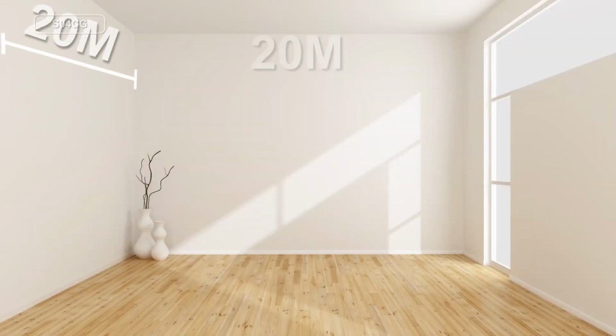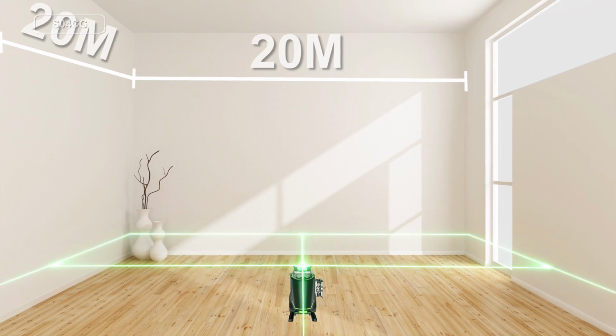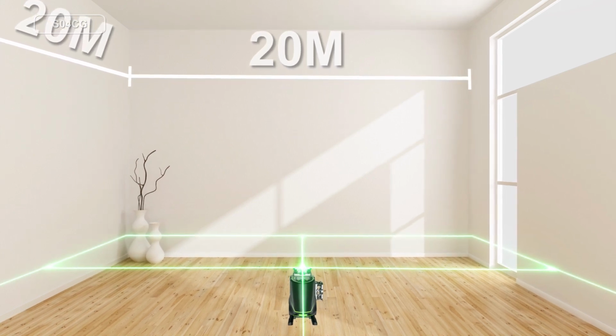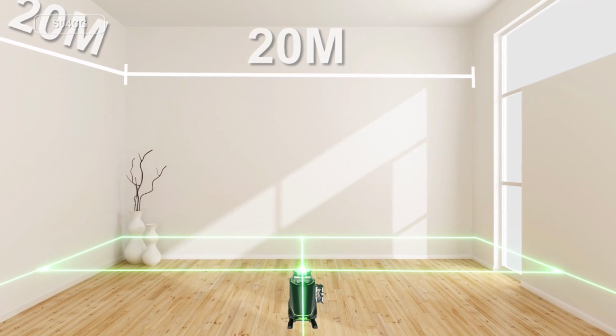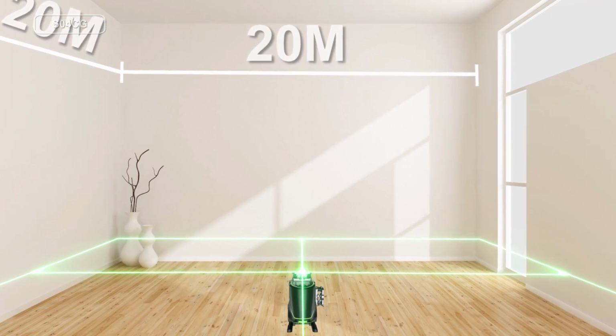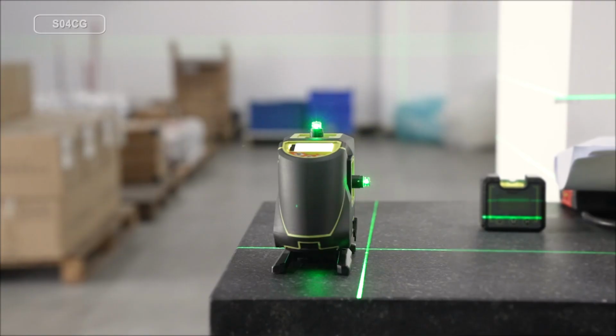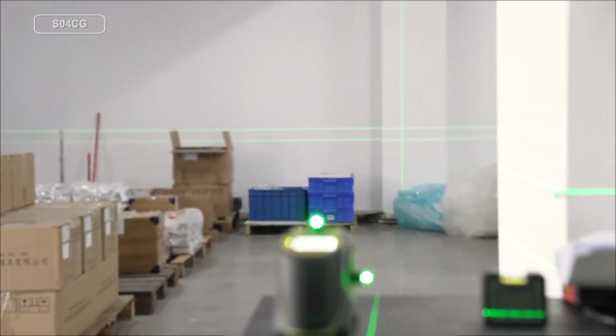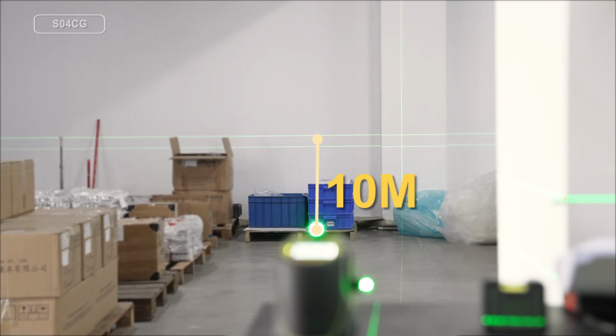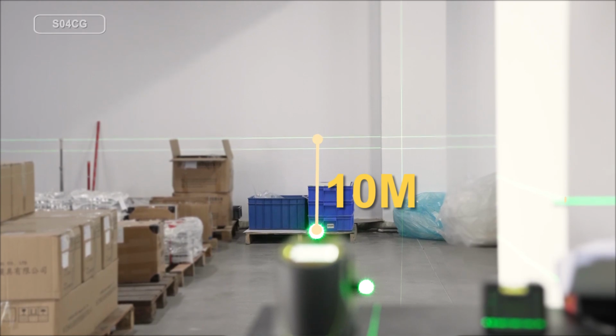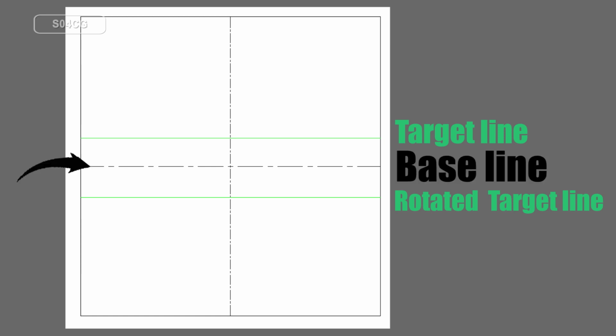In a 20 meter x 20 meter room, put the line throwing instrument in the center, open the laser, observe the position relationship between the laser line and the reference line, and adjust the accuracy according to the adjustment method. If there is no standard room, a wall with a distance greater than 10 meters can be used to ensure that the laser line is 10 meters away from the line projector. Mark it on the wall and then turn the laser 180 degrees, then make another mark on the wall. Then take an intermediate value as the reference line.